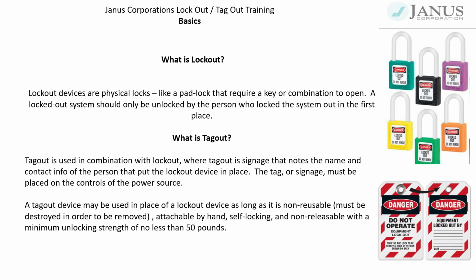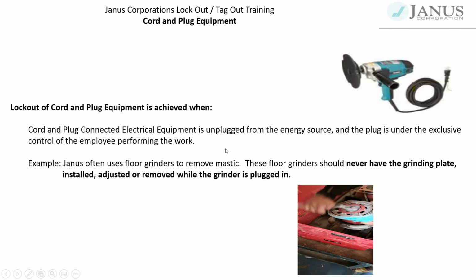A tagout device may be used in place of a lockout device as long as it is non-reusable, must be destroyed in order to be removed, attachable by hand, self-locking, and non-releasable with a minimum unlocking strength of no less than 50 pounds. Lockout of cord and plug equipment is achieved when cord and plug connected electrical equipment, such as floor grinders, are unplugged from the energy source and the plug is under the exclusive control of the employee performing the work. An example of this, Janus often uses floor grinders to remove mastic.